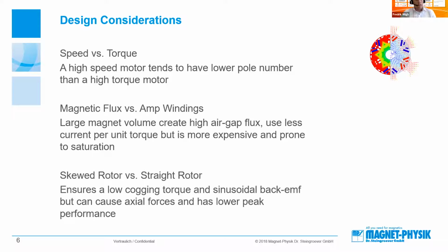The third point I listed here is the skewed rotor versus the straight rotor. By skewing the rotor, you can ensure a low cogging torque and maybe a sinusoidal back EMF, but it can cause axial forces, and for sure it has lower peak performance than the straight rotor.